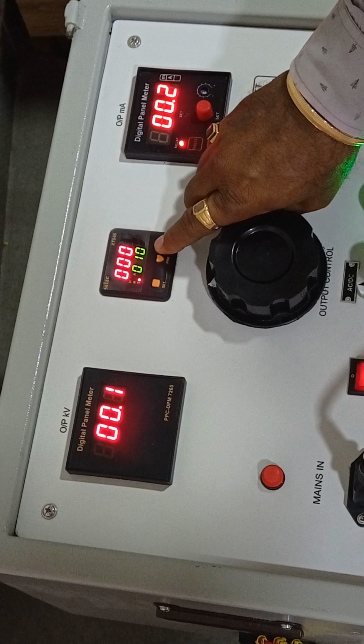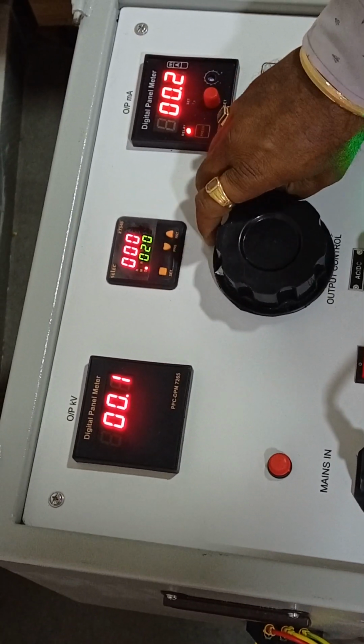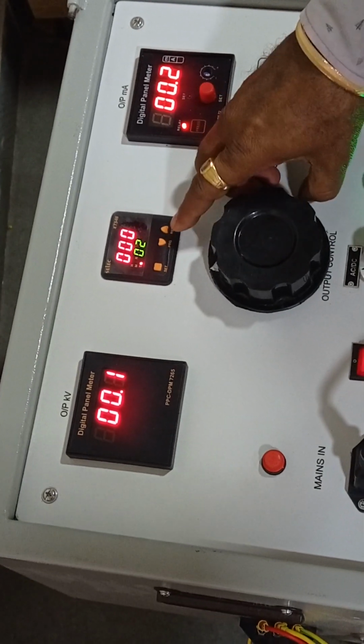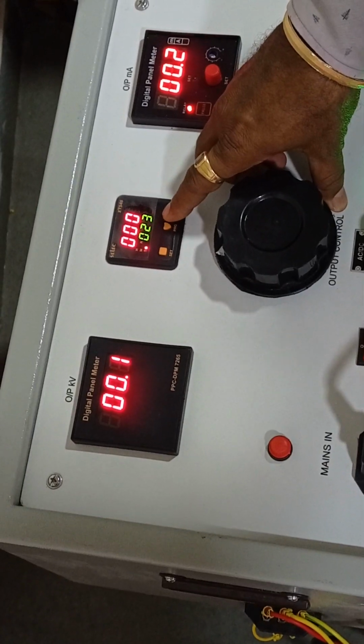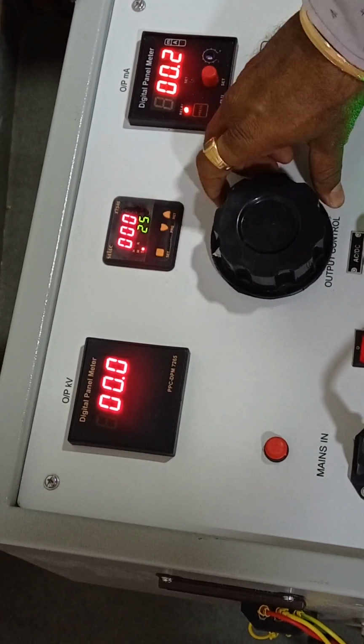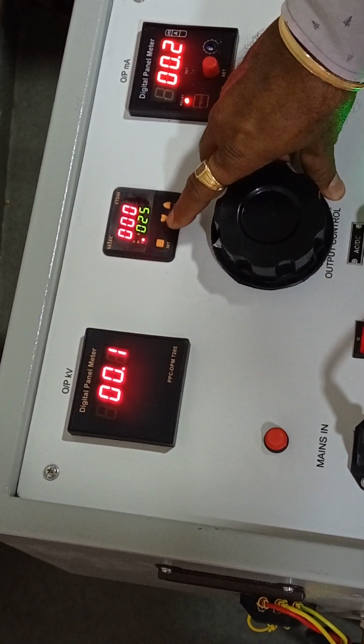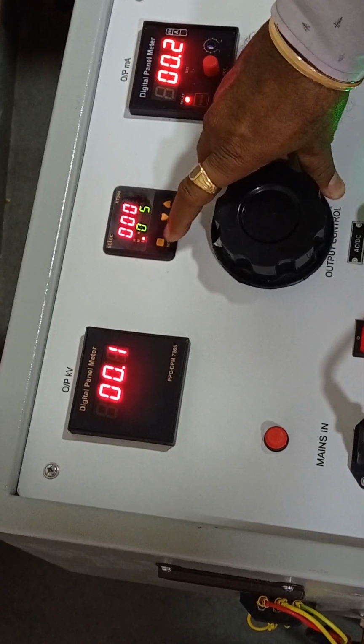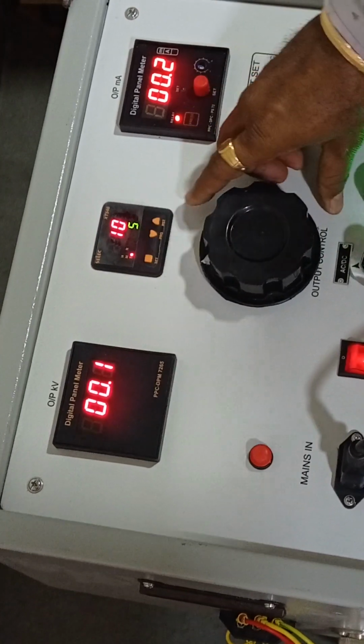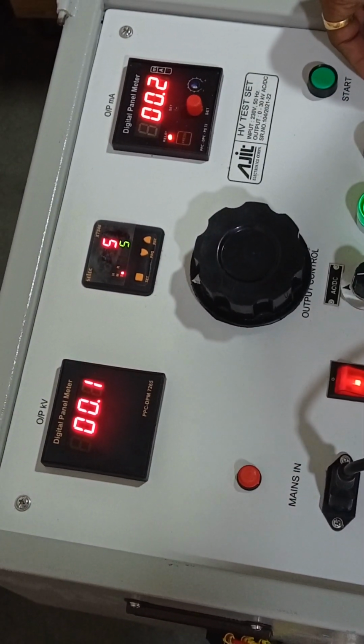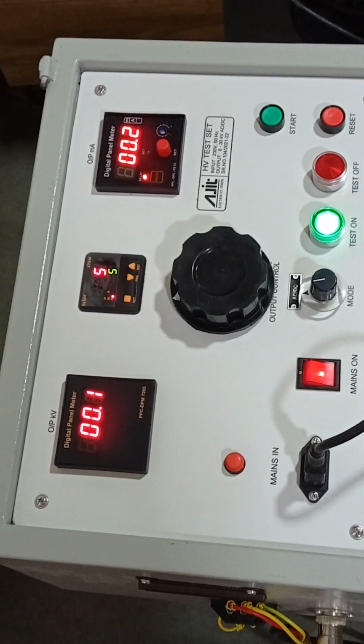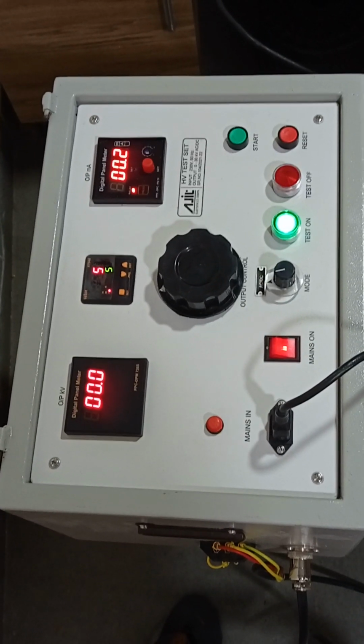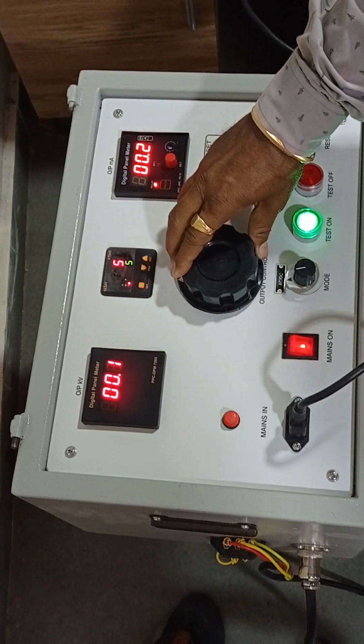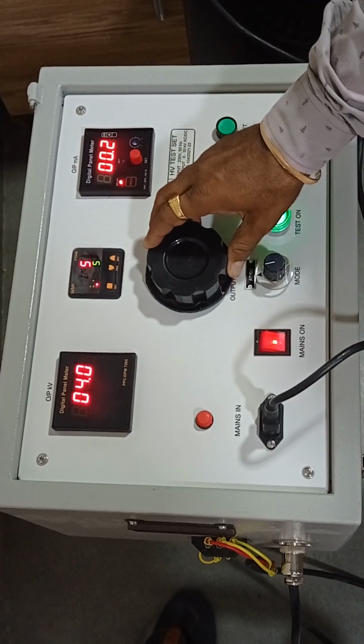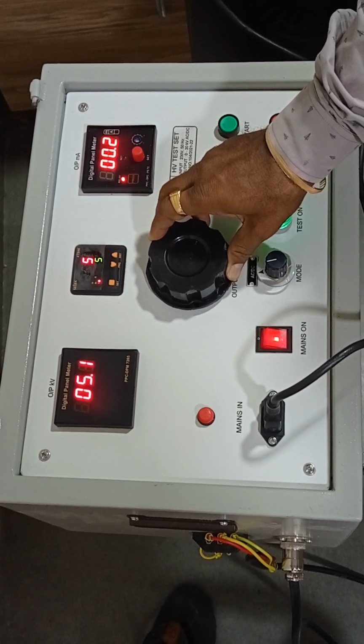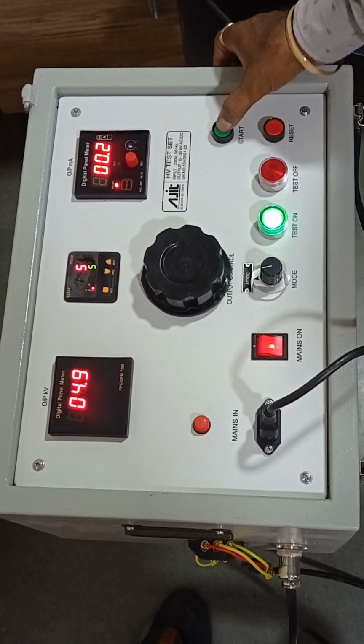Suppose we want 20 seconds, press. Now this digit will flash, so we can set it like this. If we want say 25 seconds, okay, let us consider we want to set only 5 seconds, so this way. And finally you can press and hold this key, and reset. Now 5 seconds are set. This is the duration of testing for the object. Now the high voltage is there, and we set the output voltage to, for example, 5 kV, and now we need to start the timer.